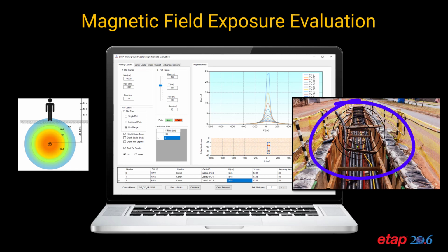By calculating the current flowing through every single conductor or entering that value, the program can determine the magnetic field strength around these cables. The magnetic field strength can then be compared against limits, such as public limits, individuals with medical conditions, or workers who are working nearby these conductors to ensure their safety and to maintain compliance.